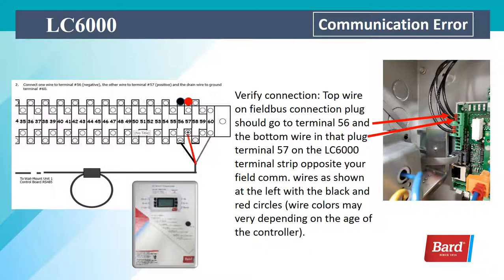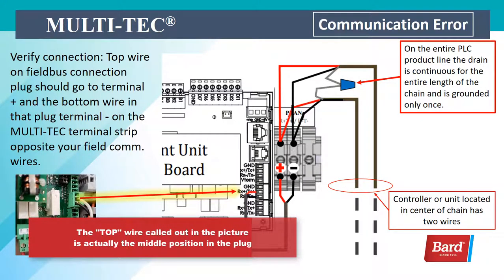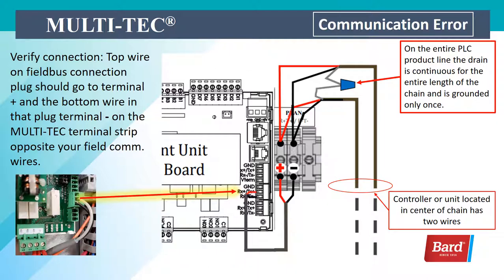Wire colors on the PLC may vary depending on the age of the controller. If you're working with a Multi-Tec, the top wire on the field bus connection plug should go to the terminal marked positive, and the bottom wire to the terminal marked negative on the Multi-Tec terminal strip — opposite your field connection wiring. On the entire PLC product line, the drain is continuous for the entire length of the chain and is grounded only once. The controller or unit located in the center of the chain has two wires; the ends only have one wire entering the unit or controller.